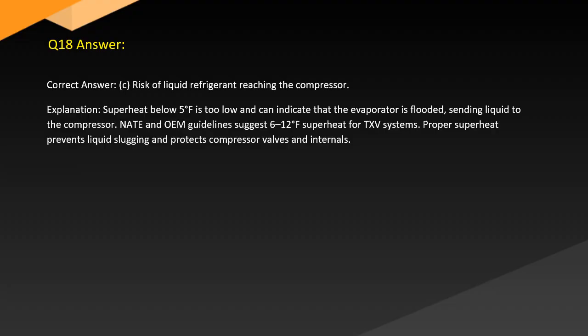Answer. Correct answer: C. Risk of liquid refrigerant reaching the compressor. Explanation. Superheat below 5 degrees is too low and can indicate that the evaporator is flooded, sending liquid to the compressor. OEM guidelines suggest 6 to 12 degrees superheat for TXV systems. Proper superheat prevents liquid slugging and protects compressor valves and internals.